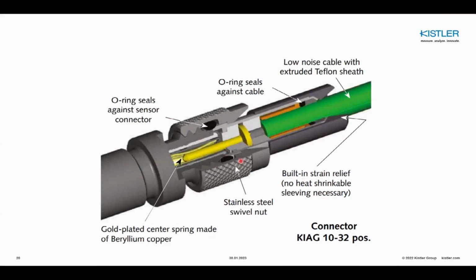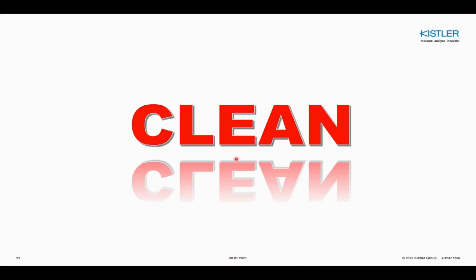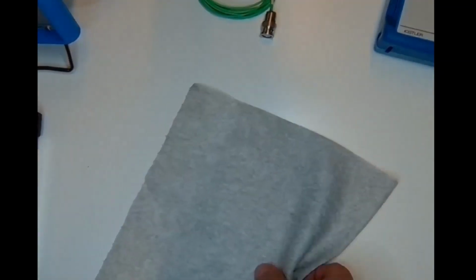So what to do to ensure the longevity of your cables? What to do to keep the measurement right? The answer is really very simple. Clean. Clean sensor connectors, clean cable connectors, keep everything in a safe, dry environment without oil. So how to clean the sensor? You can use some non-woven textile and the spray. So here we have the non-woven textile and the cleaning spray.